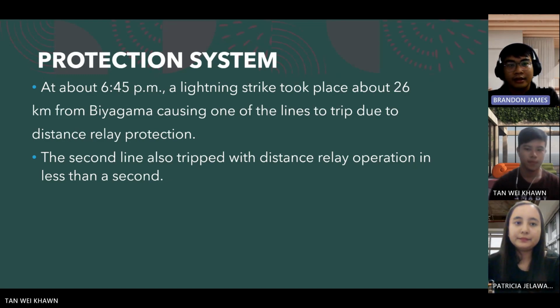Protection system. At about 6:45 p.m., a lightning strike took place about 26 kilometers from Biyagama, causing one of the lines to trip due to distance relay protection. The second line also tripped with distance relay operation in less than a second.